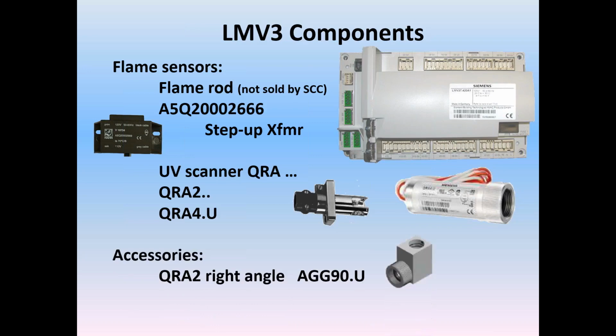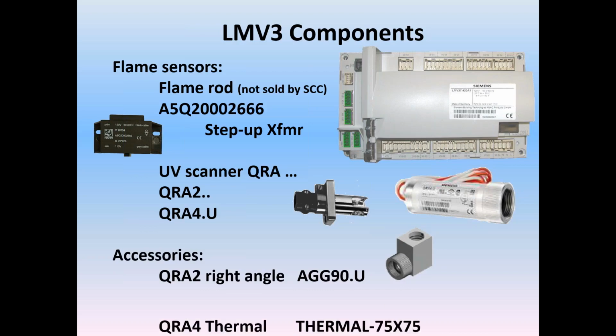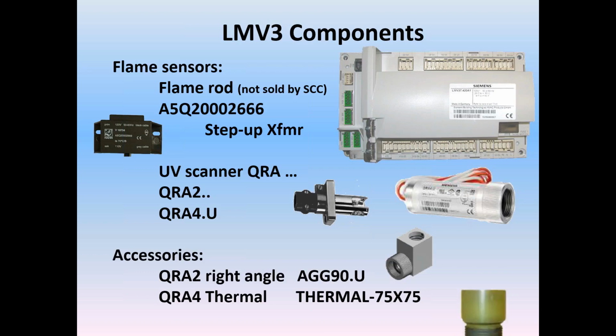Additionally, if you take the QRA2, you can use a right angle adapter to kind of push it out of the way or put it straight in, whatever you see fit for your application. Or the QRA4 also has a thermal connection, which you'd put on the end, and that would give you thermal protection from the burner to the scanner. All the devices on the LMV3 series and all of the Siemens controls have a 140 degree Fahrenheit temperature limitation. So if you get a hot sight tube on it like that, you could put a thermal standoff, and then your scanner will stay below the 140 degree limitation.